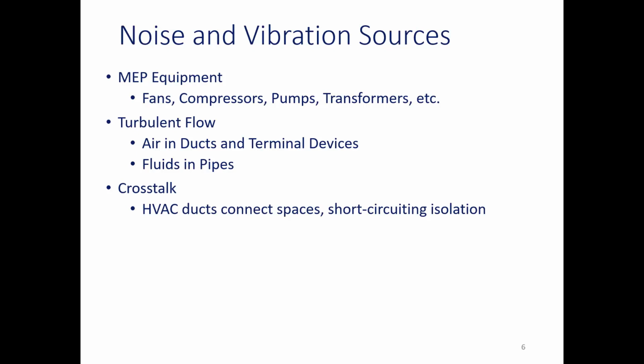So here we just have a list of equipment that could be noise and vibration sources. So fans, compressors, pumps, transformers, other things, cooling towers, condensing units, etc. Turbulent flow is another, so this is what's happening in the ductwork or as the air is leaving or entering the ductwork. You have air that's going too fast and too complicated turns. You don't have full radiuses. You don't have the proper separation between them. If you have that complicated ductwork at high speeds, you get turbulent noise that propagates through the ductwork just like the fan noise does.